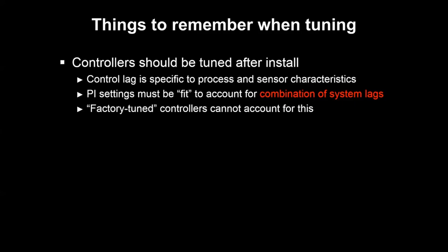So a few things to remember. First is that controllers really need to be tuned. You may hear things like a factory tuned controller is good to go out of the box, but one thing we want to stress is that you have these systems of lags. If you have something like a pipe sensor probe that's in a well, in a piece of pipe, you can imagine there's a certain thermal lag associated with it. You want your control system to be tuned to handle that, so that it's not constantly overshooting or cycling or not accounting for that specific set of lags in your system.